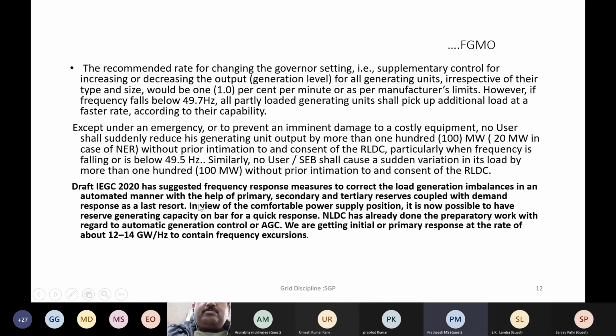Right? So how does the megawatt affect the MVAR by changing the megawatt? It doesn't affect the MVAR generating, right? No, it doesn't. Both are independent. Then how will it help in reducing the MVAR of the generating units? No, by changing the governor set point, MVAR doesn't change unless you also change the AVR set points at the same time.